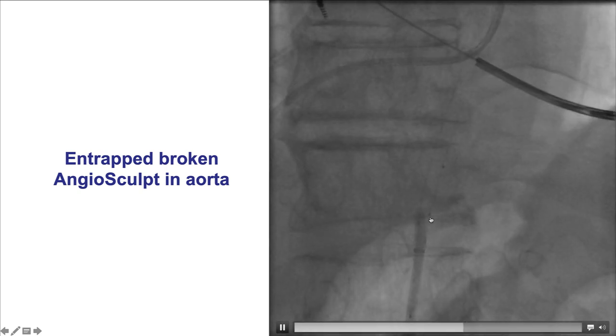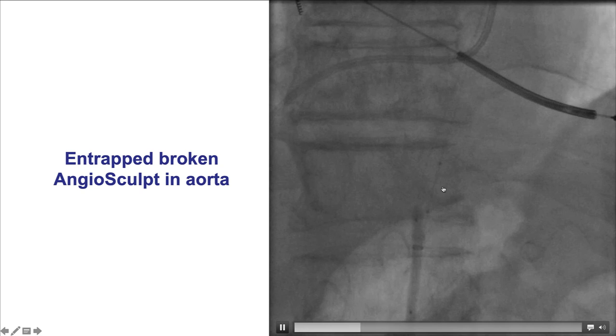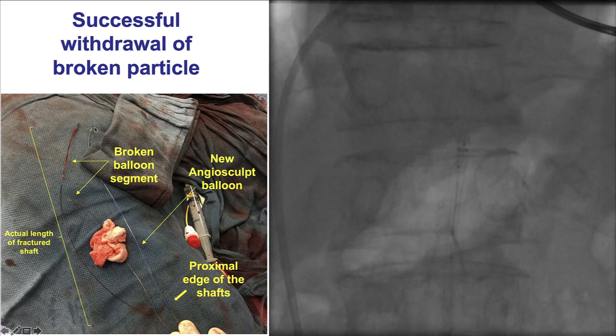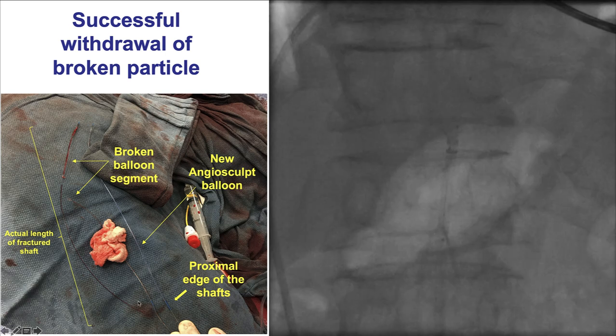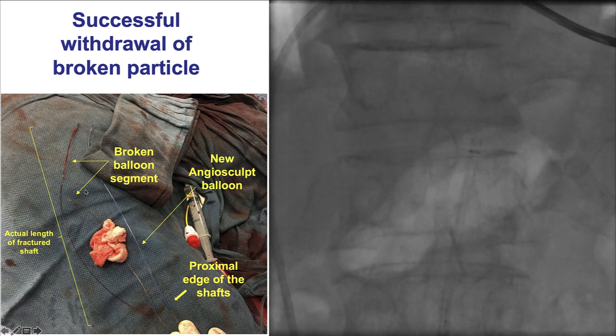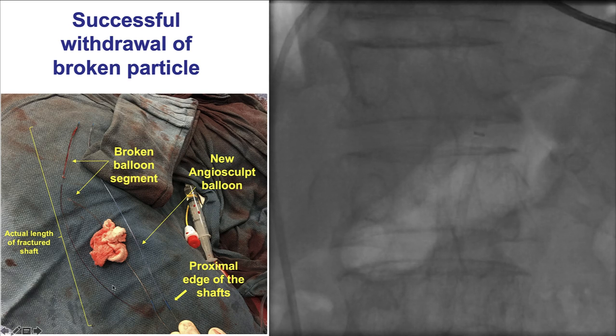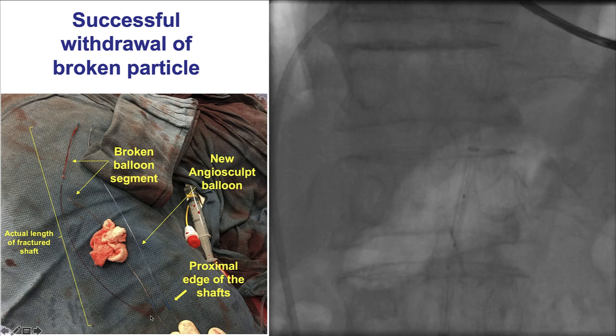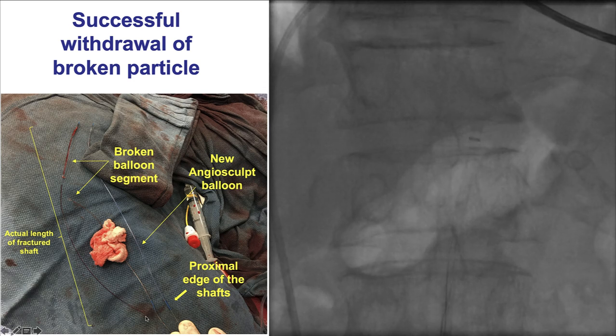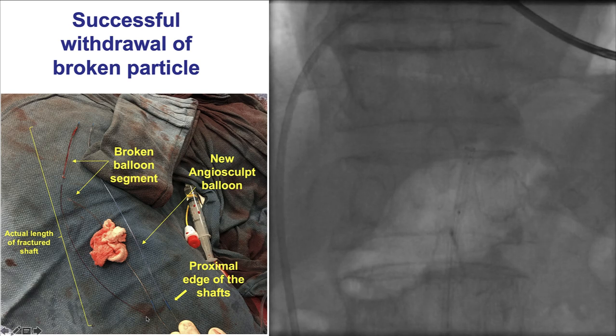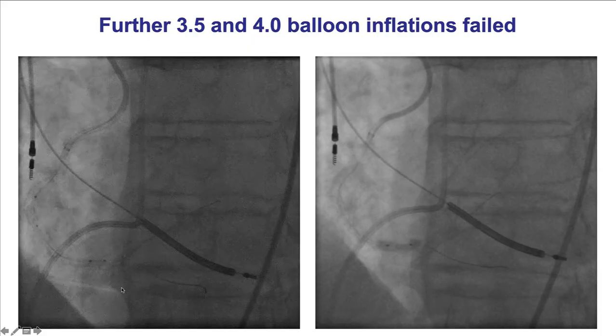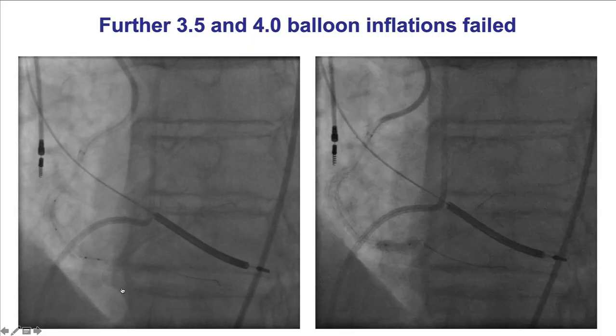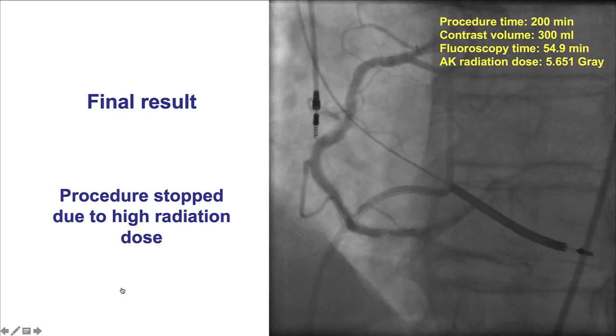It was a fairly lengthy segment of the angiosculpt balloon that was retrieved. The lesson here is that a kink likely occurred in the angiosculpt balloon before insertion, which then led to fracture. If there is any kink in the shaft of a balloon, it should be discarded and not inserted into the body. Eventually, additional balloon inflations were performed and the case was concluded.